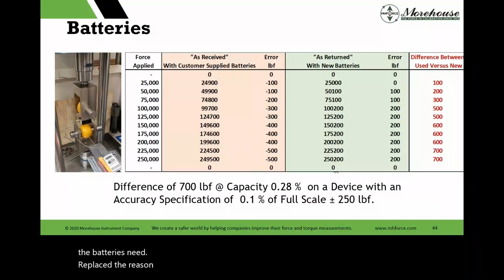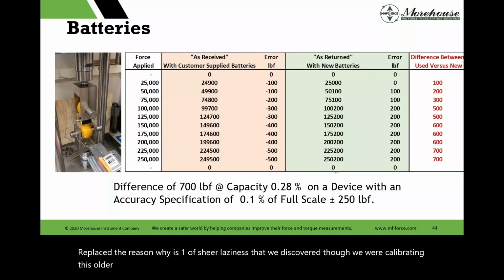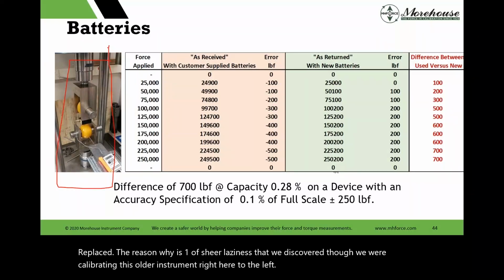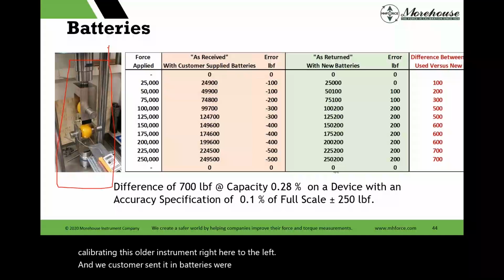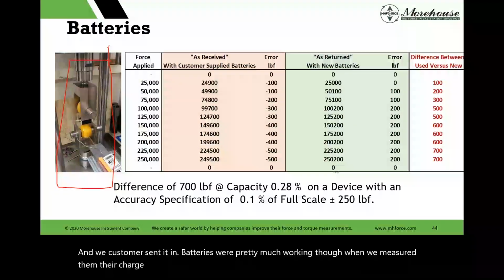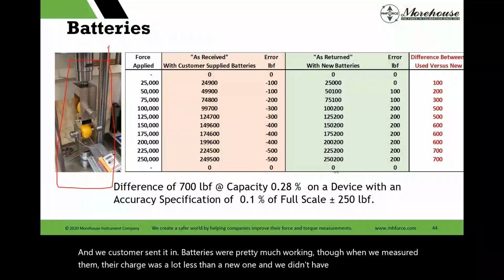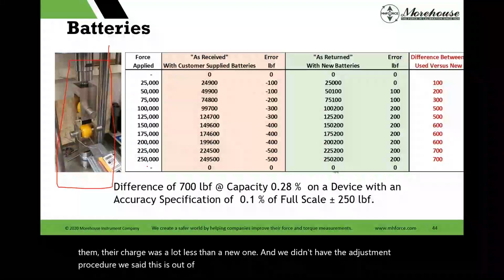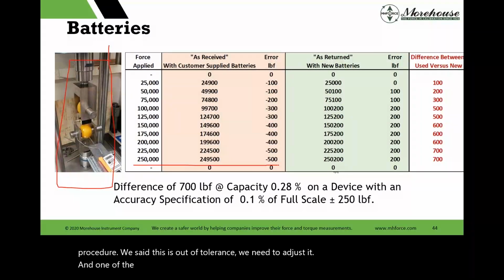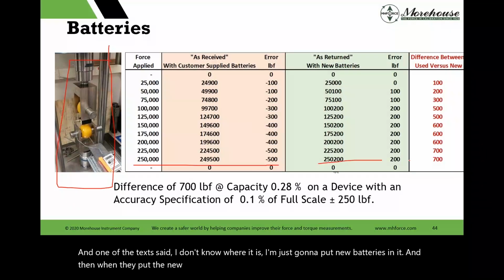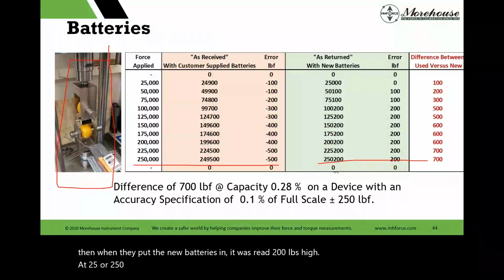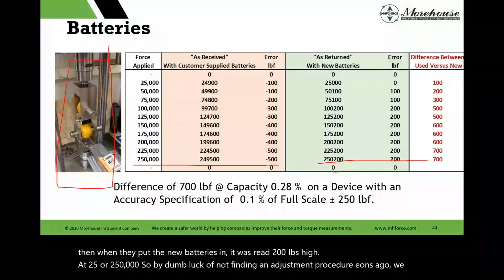The reason why is one of sheer laziness that we discovered. We were calibrating this older instrument right here to the left, and the customer sent it in. The batteries were pretty much working, though when we measured them, their charge was a lot less than a new one. And we didn't have the adjustment procedure. We said, this is out of tolerance. We need to adjust it. And one of the techs said, I don't know where it is. I'm just going to put new batteries in it. And then when they put the new batteries in it, it read 200 pounds high at 250,000. So by dumb luck of not finding an adjustment procedure eons ago, we basically changed our policy and procedure.